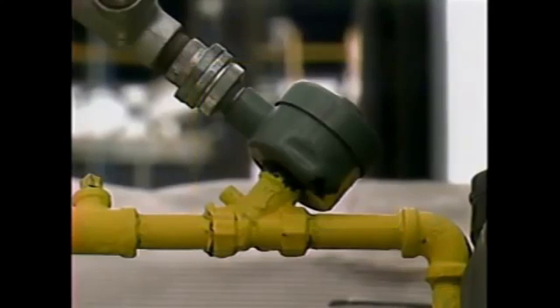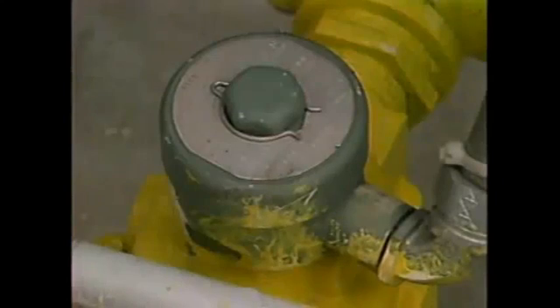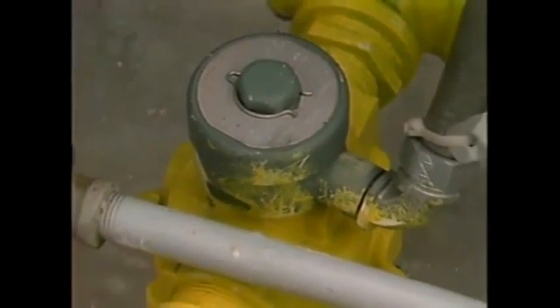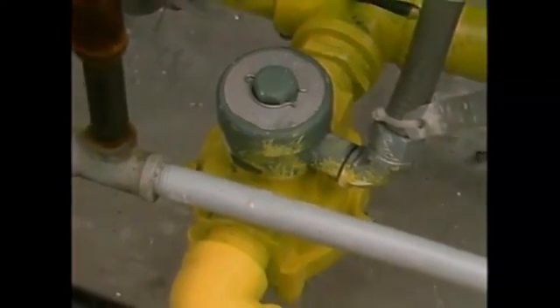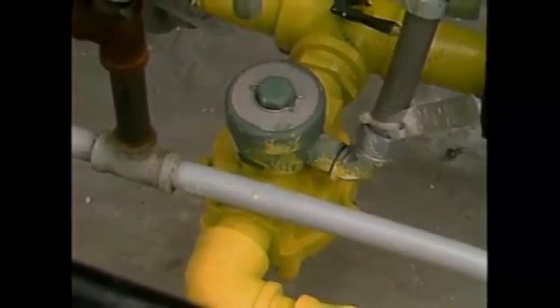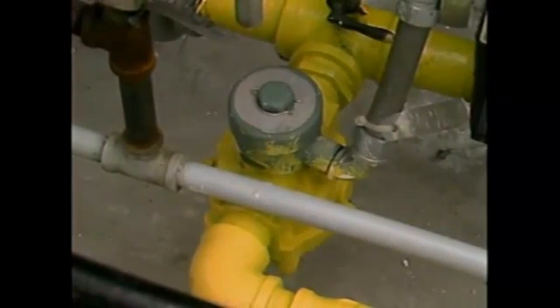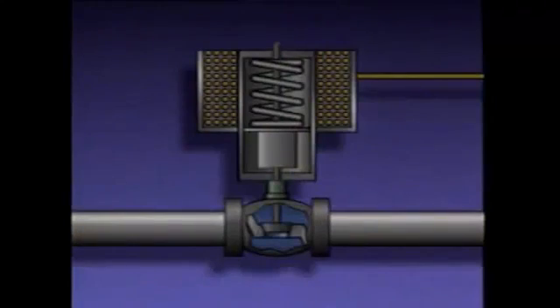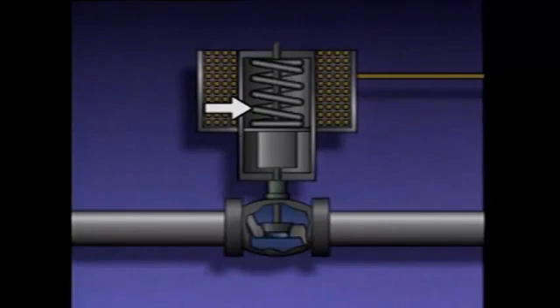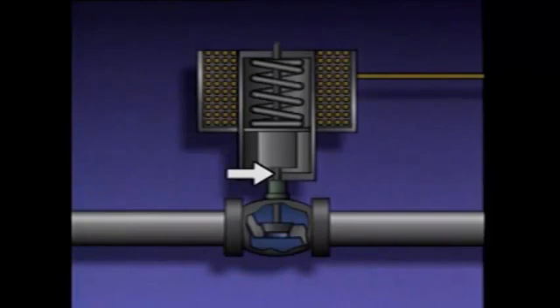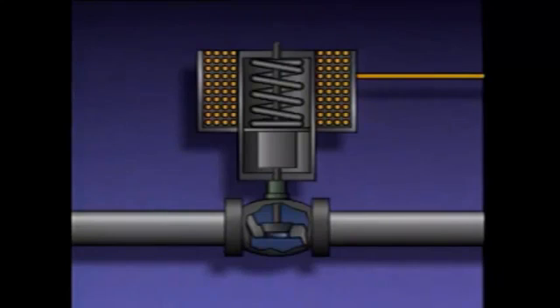A solenoid actuator, or simply a solenoid, is typically used for on-off control of a valve. Solenoids can position a valve from fully open to fully closed quickly, making them particularly useful for emergency shutoff. A solenoid actuator consists of a wire coil, a spring, an armature or core, and a stem which is connected to a valve.